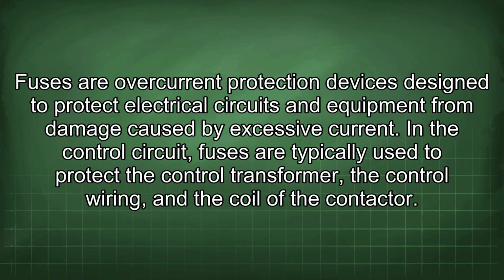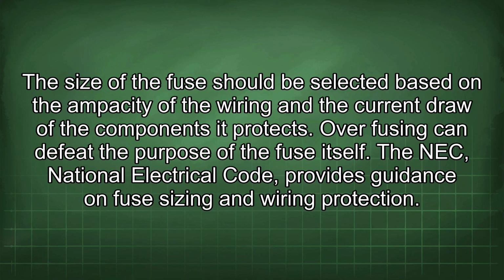Fuses are overcurrent protection devices designed to protect electrical circuits and equipment from damage caused by excessive current. In the control circuit, fuses are typically used to protect the control transformer, the control wiring, and the coil of the contactor. The size of the fuse should be selected based on the ampacity of the wiring and the current draw of the components it protects. Overfusing can defeat the purpose of the fuse itself. The NEC, National Electrical Code, provides guidance on fuse sizing and wiring protection.